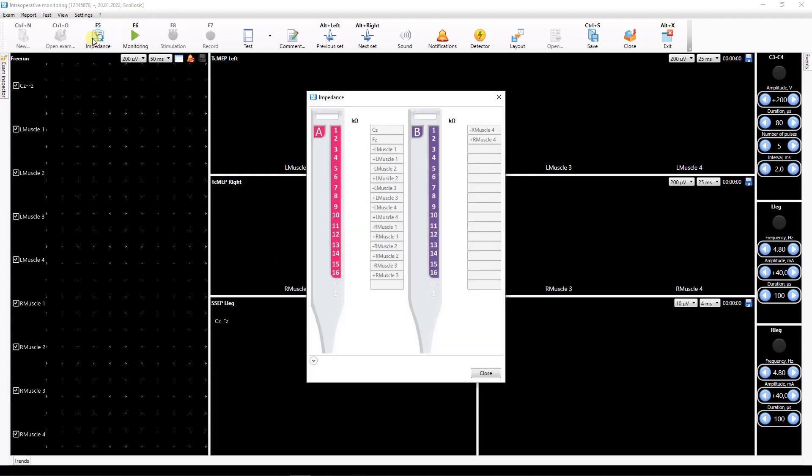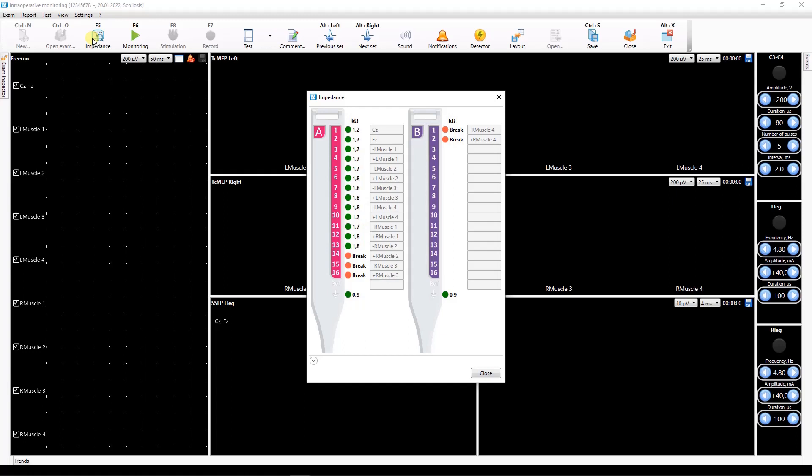Place the electrodes in accordance with the sites indicated in the test template. Check electrode placement quality by clicking the impedance button on the toolbar. In the opened window you will see the impedance values of the used sites. Green indication means good electrode contact. If you see red indication check if the corresponding electrode is applied correctly.